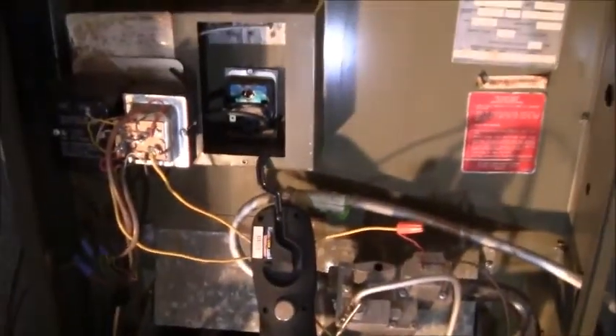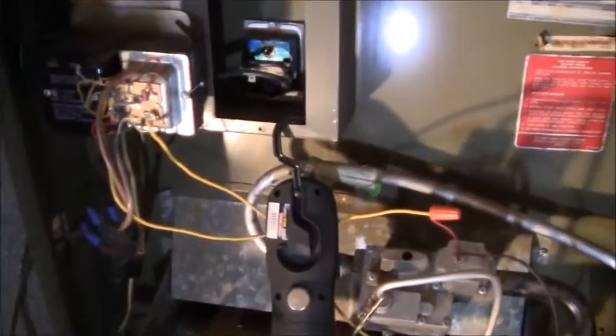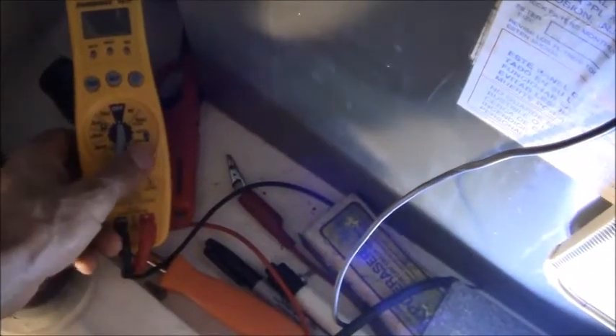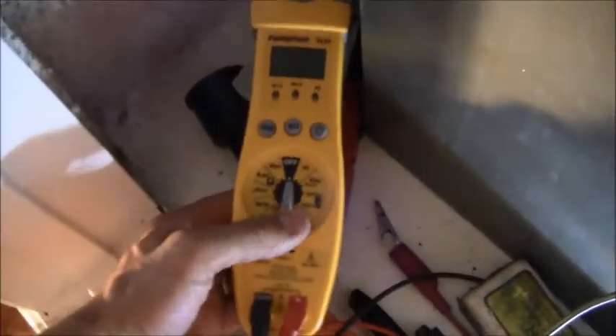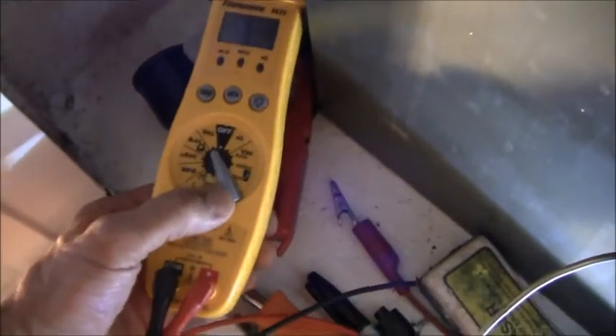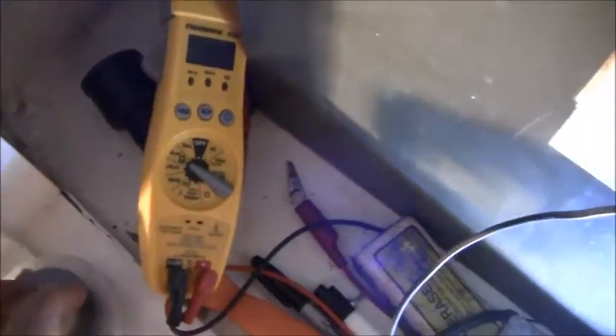So this way I could put two lines on the same leg, bypassing that thermostat. Once I plug this in, the fan is going to start in heating mode. Then I'll be able to populate my sheet with all the data. So that's exactly what we're going to do now. I've got an amp probe on here, so I can go ahead and put that on AC amps right there. I'm going to go ahead and plug this in.